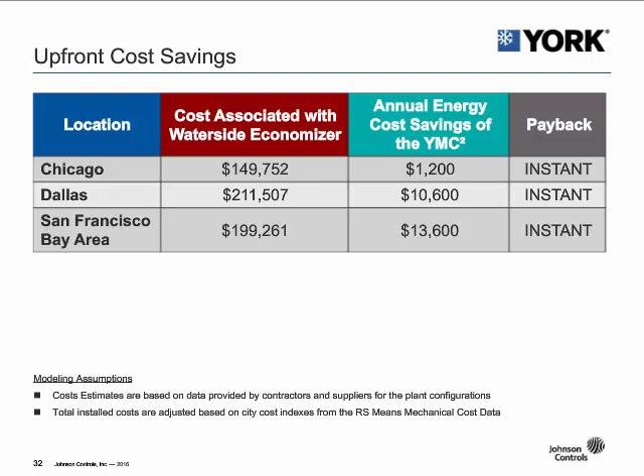I would say everything has to be evaluated at the same time. Yes, at colder tower water, the Waterside Economizer will still come into play, but we're delivering a system design that can eliminate the Waterside Economizer altogether and still provide a more efficient plant. But yes, if you do have an existing Waterside Economizer, like we mentioned in the slide deck, most certainly use that for your free cooling application. But if there is an increased building load or retrofit in the future, just know you have a chiller that is capable of an increased load or just working hand in hand with the free cooling heat exchanger.